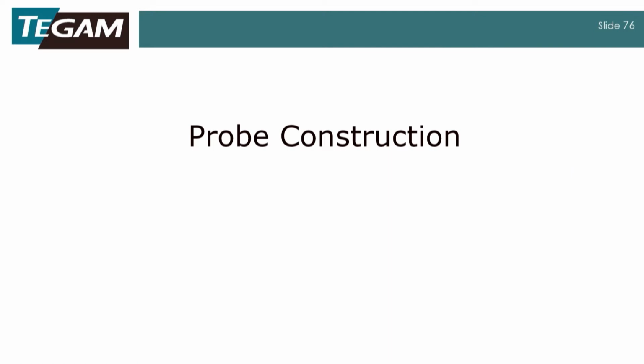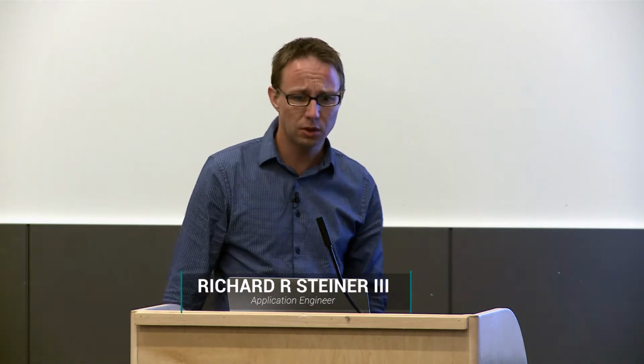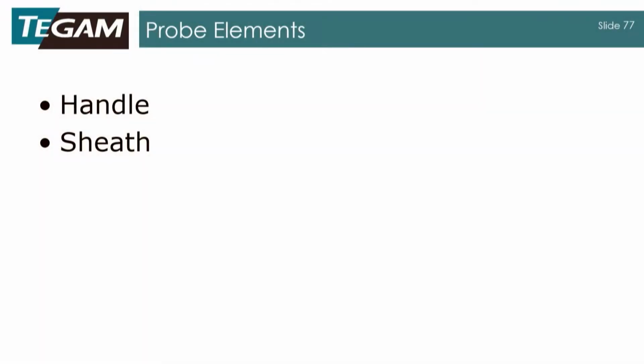So the next topic of discussion here is going to be the other side of instrumentation. That's going to be your probe construction. Our probe is going to be made up of various elements. You're going to have the handle. This is the part that you hold. The sheath, that's the other side that's going to hold your temperature sensing element. The junction, which basically is how your sheath is going to be attached to your temperature sensing device, and we'll get into that here.